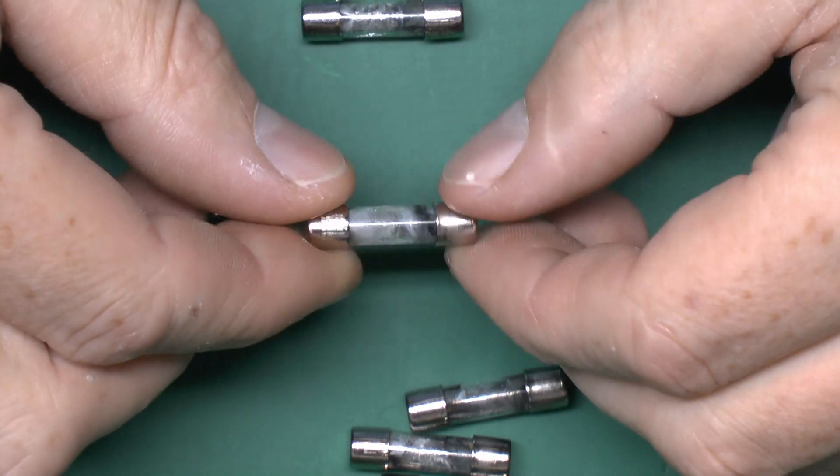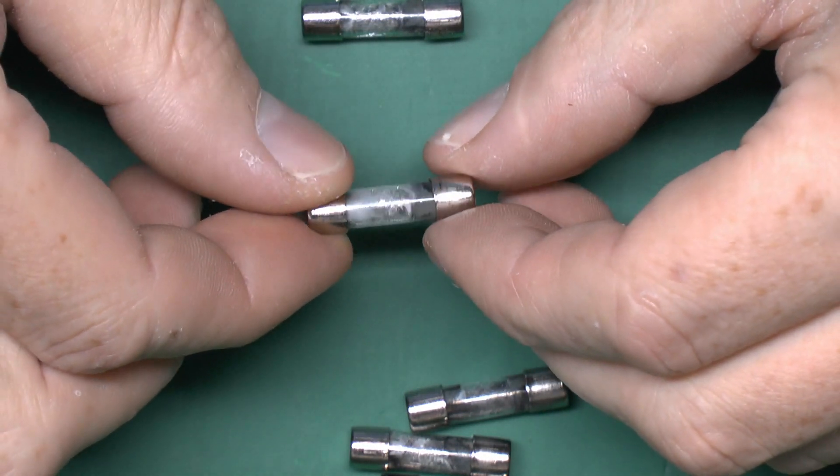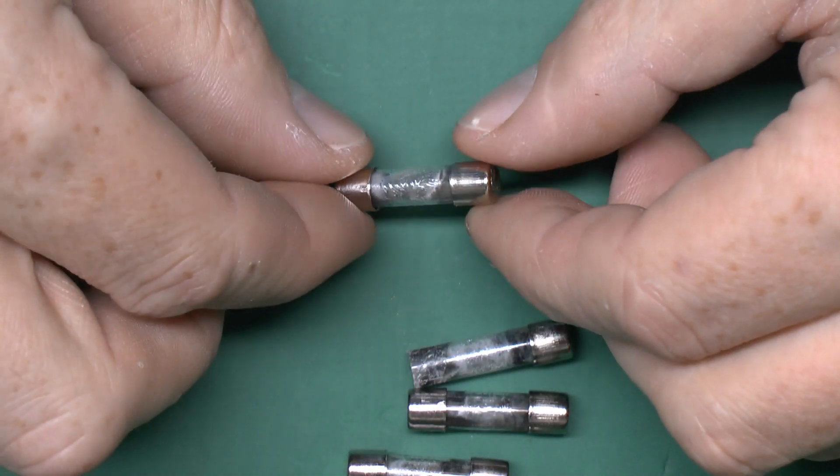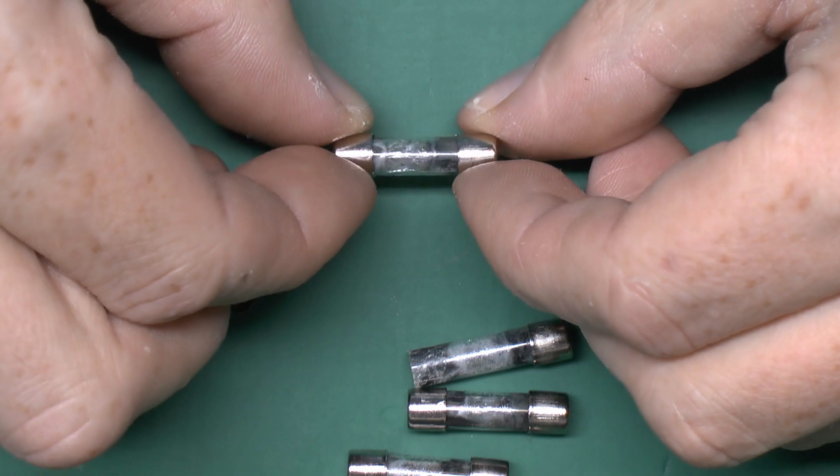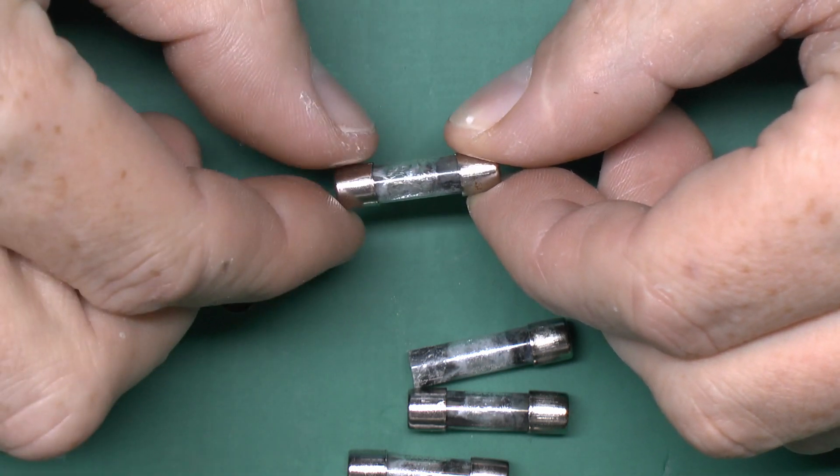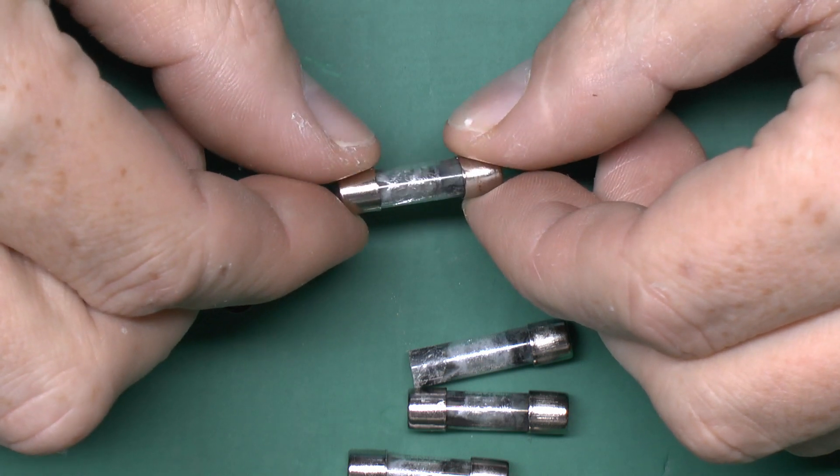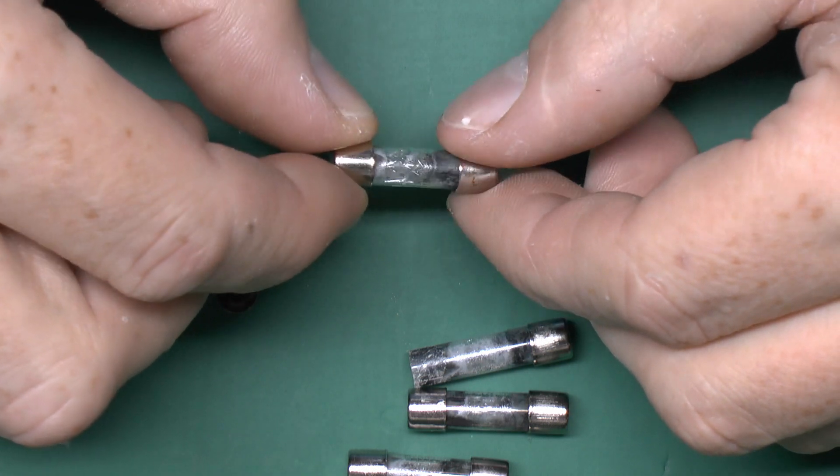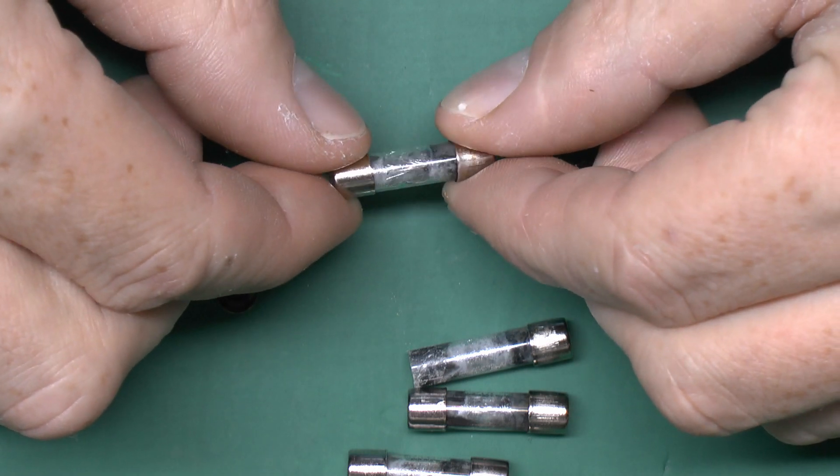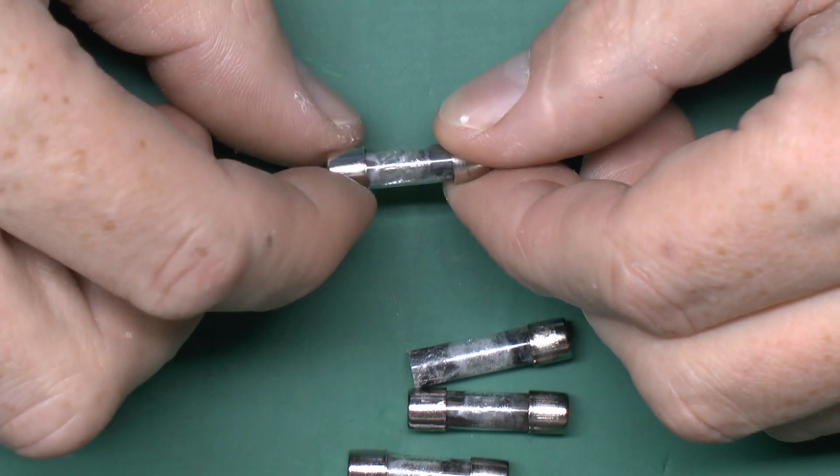And quite why that particular end came off is not clear. But nevertheless that's certainly a failure. And this is one used right at the end there which is difficult to see. But it does have some actual fractures. There's one there just in the glass itself. So fairly clearly if the fault current had been a bit higher which of course it would be if you were using actual mains voltage then that would definitely have broken and crumbled to pieces.